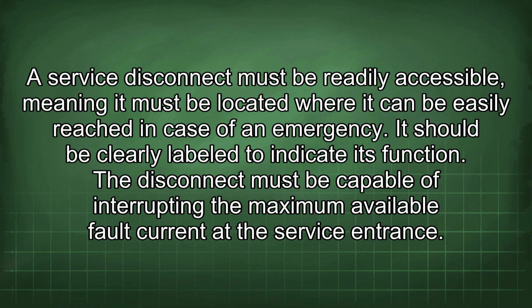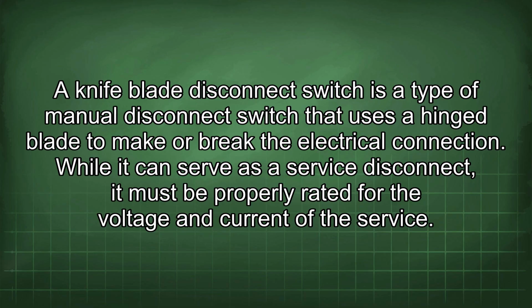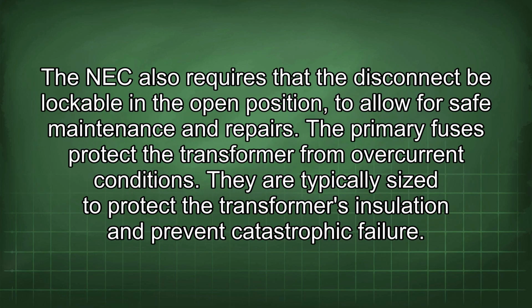A service disconnect must be readily accessible, meaning it must be located where it can be easily reached in case of an emergency. It should be clearly labeled to indicate its function. The disconnect must be capable of interrupting the maximum available fault current at the service entrance. A knife blade disconnect switch is a type of manual disconnect switch that uses a hinge blade to make or break the electrical connection. While it can serve as a service disconnect, it must be properly rated for the voltage and current of the service. The NEC also requires that the disconnect be lockable in the open position to allow for safe maintenance and repairs.